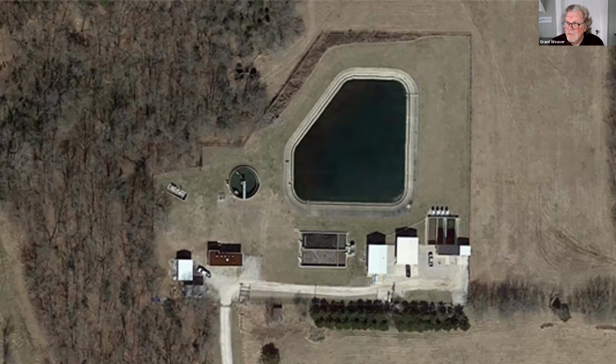It was indiscriminate, so it would come in not necessarily to the SBR tank that was being aerated, at any point in time during any cycle. It just would pump in because the SBRs were running on their own timers, and this pump was run at a certain time of the day. It would pump a given number of minutes, which was an estimate, trying to bring about 10% of the waste sludge back.